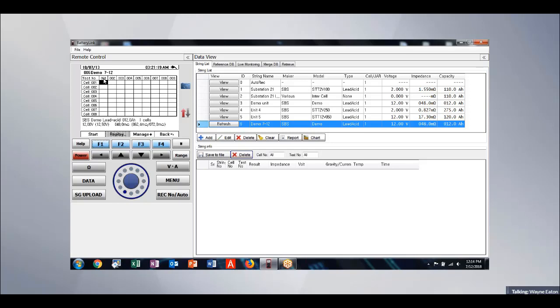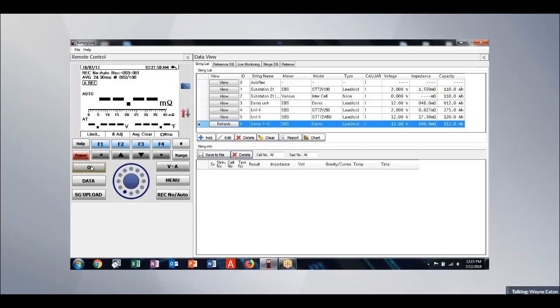But at the same time, it's going to allow me to record up to 100 historical tests on that battery system. So I can literally go to a substation every quarter for 20 years, record all that data, and trend the entire life of the battery system. And this is a feature none of the other units have in their software or in the unit's capabilities. The ohms key takes me back into the ohms measurement mode. And in this mode, right now, you'll see that I'm recording on string 3. It's like test number 1. But we actually want to go in to that string that we just set up to take readings.